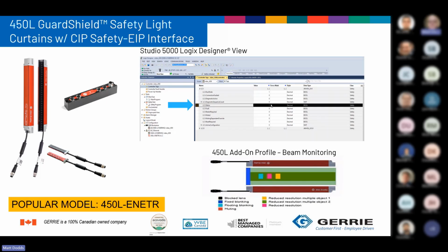And then unique to Allen-Bradley is the CIP Safety interface for the 450L light curtain. I can connect the light curtain to a safety PLC, and set up, configure, monitor and select functions through the add-on profile. So you could actually use a safety selector switch to change the functionality of the light curtain based on a pre-designated profile set up within the program.